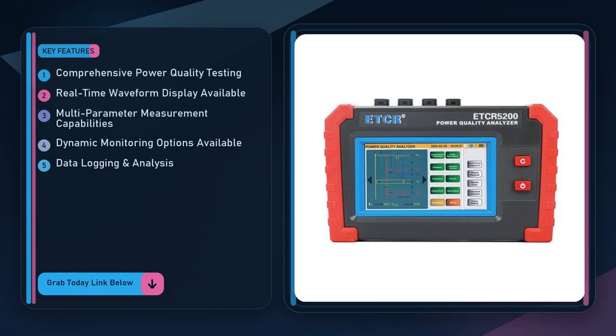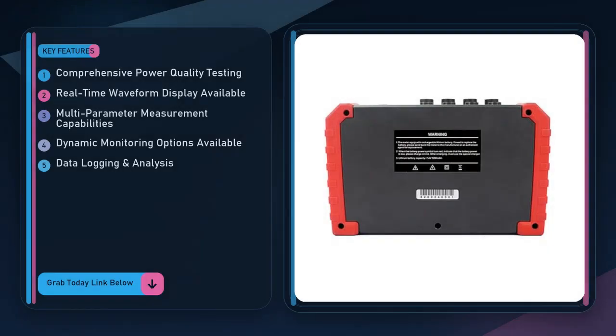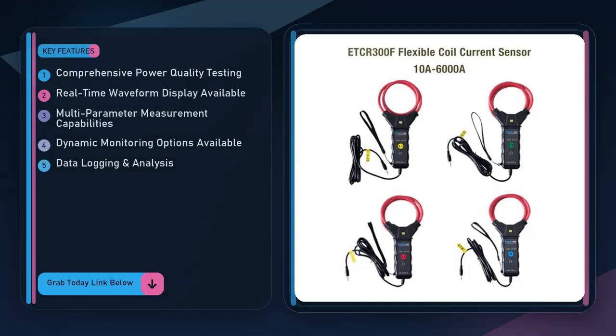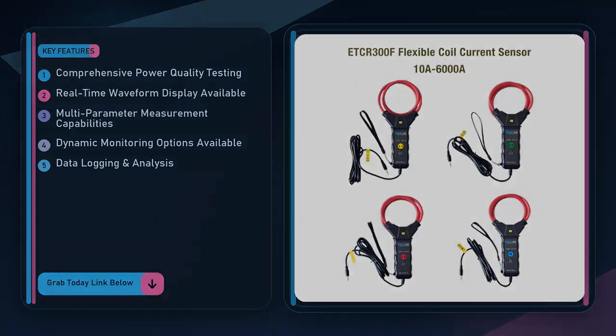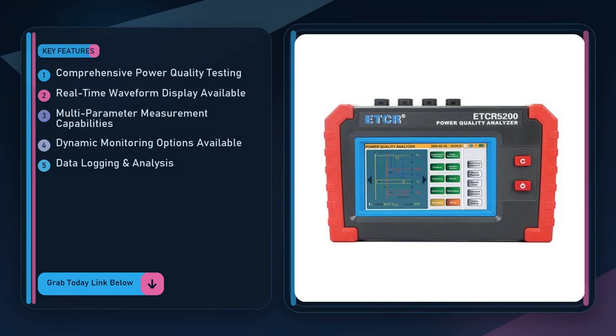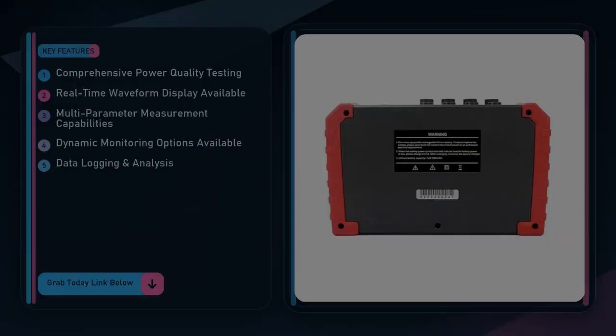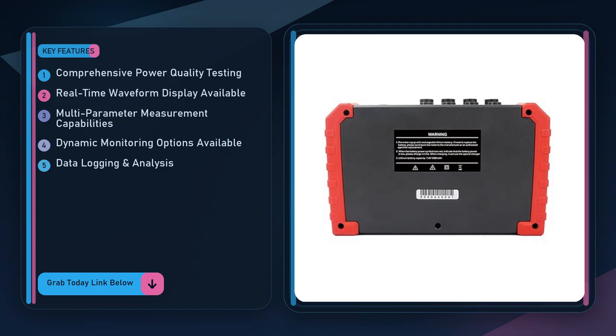Who should buy the ETCR5200? The sweet spot is small to medium industrial facilities, commercial building managers, and serious HVAC or electrical contractors who need more than a quick voltage check. If you already own a basic power meter and you're constantly calling in a specialist to interpret waveforms, this analyzer pays for itself by letting you do the diagnostics in-house. It also makes sense for research labs that need to verify power quality when testing new equipment.